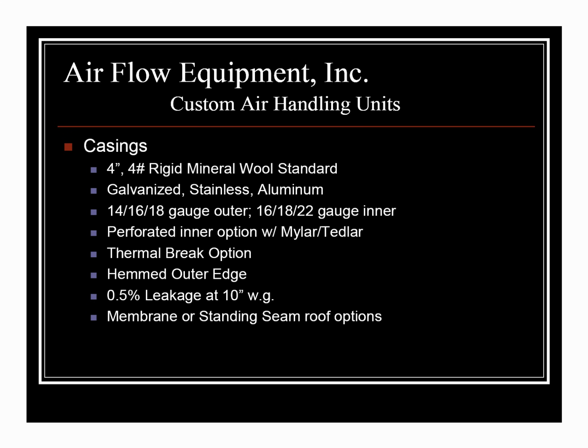One of the things we do now is we hem the outer edge of the panel for a very clean appearance, and that also helps to add to the tightness of the unit. You can see the next line talks about 0.5% leakage at 10 inches of static pressure. That's something that we test to on a regular basis, day in, day out, and we can hit that with our normal unit construction. So again, if you're looking for that tight specification, 0.5% leakage for a hospital or university, that's really where we excel, and that's the quality of unit that we build.